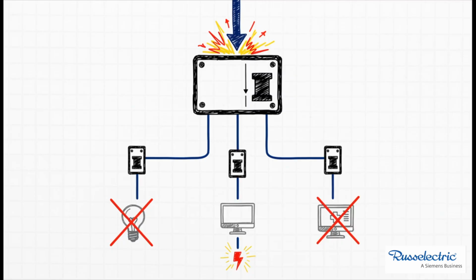This is the domino effect in action. If that big main breaker is just as fast as the tiny one protecting a single outlet, it's basically a coin toss which one trips first. And if you lose that coin toss, a tiny fault in one room has just caused a massive blackout.